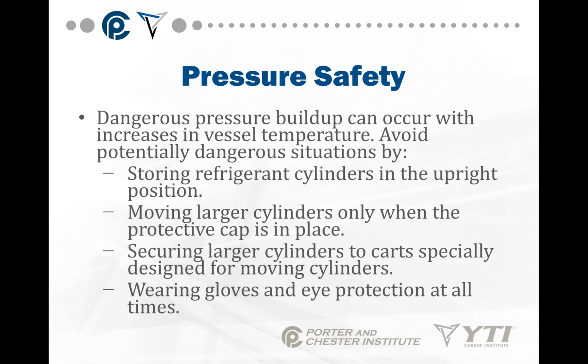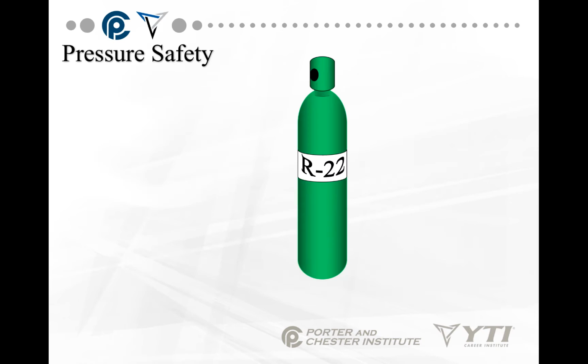Throughout this course, you're going to be dealing with pressures, okay? Pressures in containers, refrigerant cylinders, nitrogen cylinders. So we're going to start there. We can actually have dangerous pressure buildup in the vessel, which is the canisters. We want to make sure we store refrigerant cylinders in an upright position. You want to only move large cylinders like nitrogen cylinders with the protective cap in place. We want to make sure we secure them to carts. Don't try dragging them across the floor. And we want to make sure we wear gloves and eye protection anytime you're handling a refrigerant.